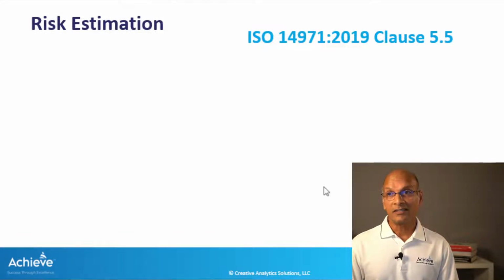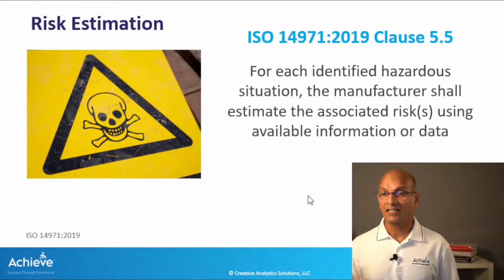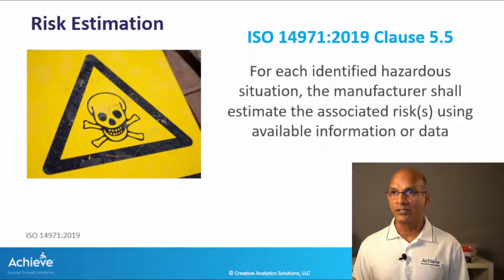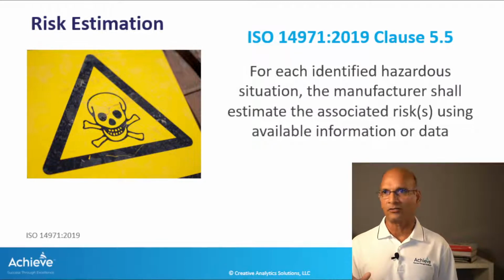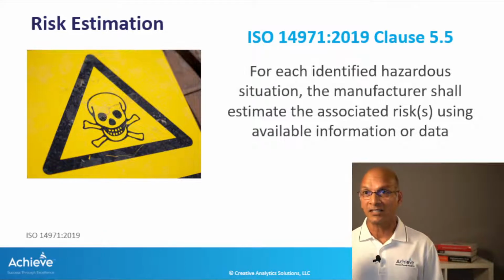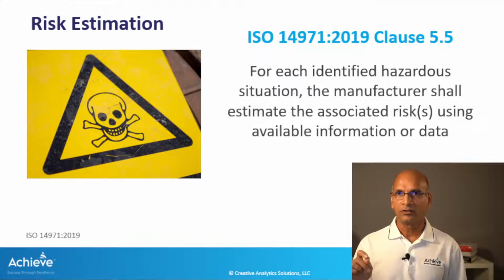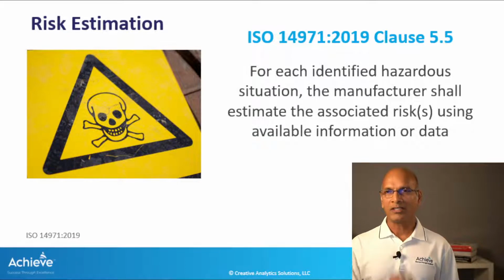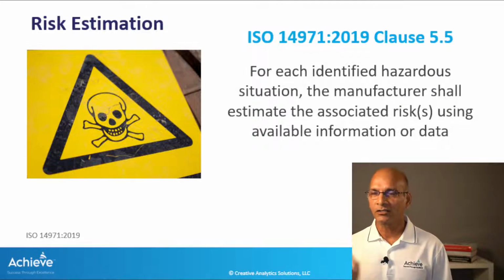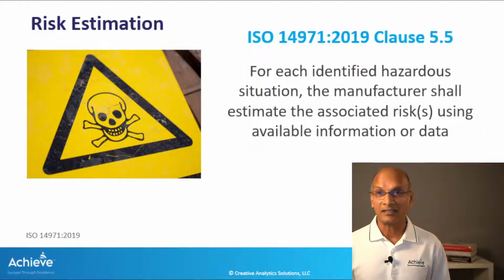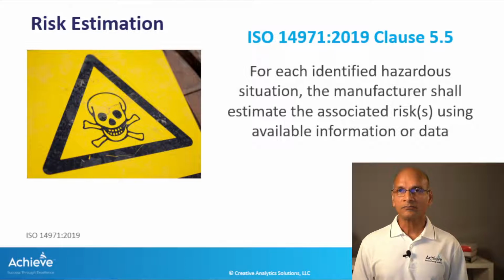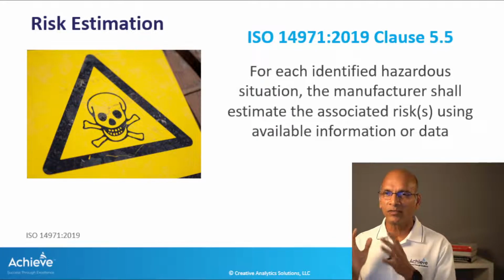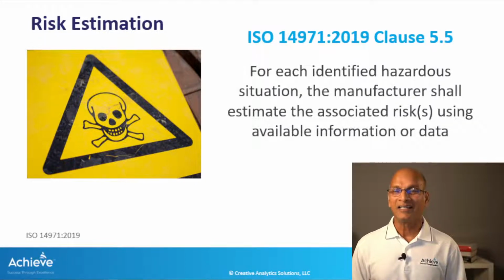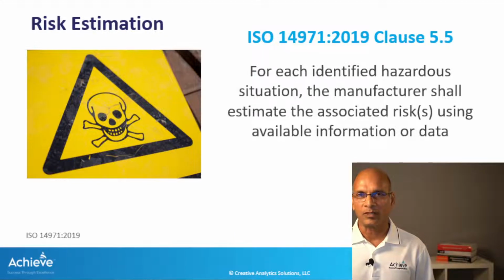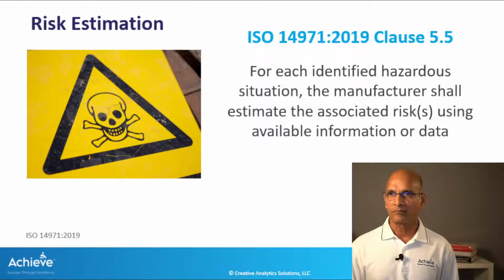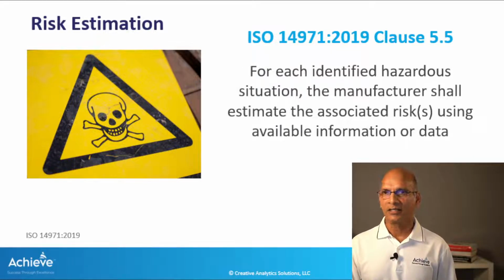So risk estimation is a requirement. For each identified hazardous situation, the manufacturer shall estimate the associated risks using available information or data. Shall means it's mandatory. And remember, they are saying for each identified hazardous situation. So it's important for us to clearly show what is the hazardous situation, what are the applicable hazards, what is the harm, and what is the risk of that harm. That's what ISO requires, right? We talked about hazard analysis in one of our recent live discussions. Where we get confused about this is when we try to estimate the risk of harm for ISO 14971 inside an FMEA. That's where there's a lot of problem and confusion. And we can talk more about that during our discussion today. Feel free to share questions and comments as they come to your mind.